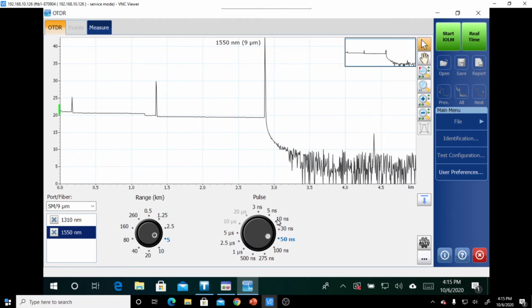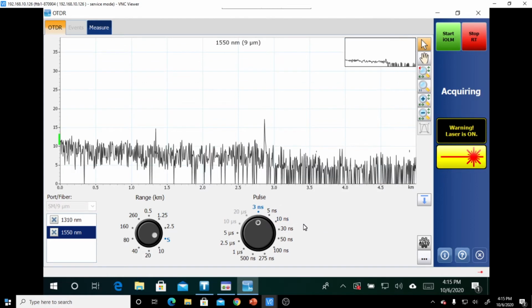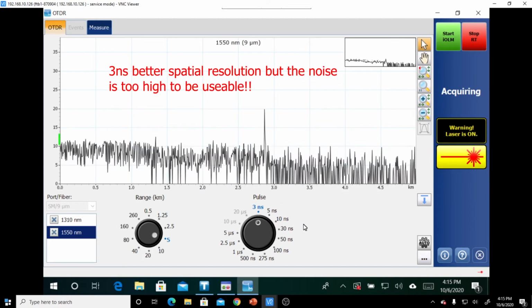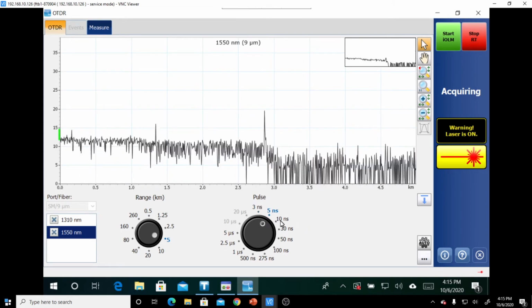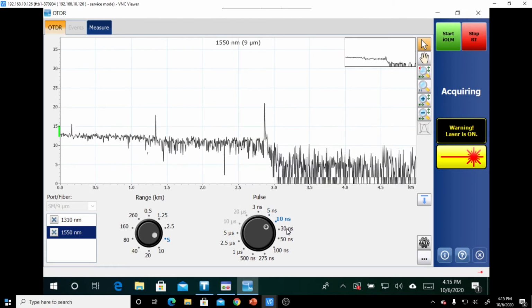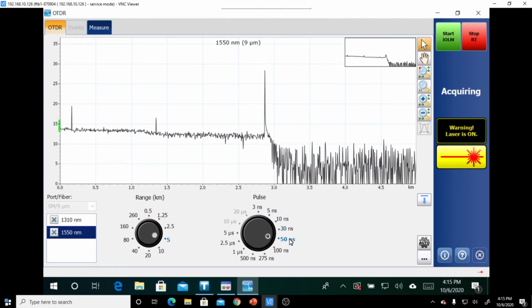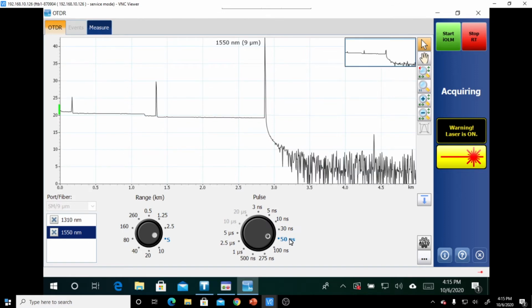Now pulse width, if it's shorter, you'll notice that it's noisier. And so at 3 nanoseconds, we get really good spatial resolution, but we do not get very much distance. So as I increase my pulse width, I'm able to see it gets cleaner and cleaner. Now, you're never going to get the resolution that iOLM gets.